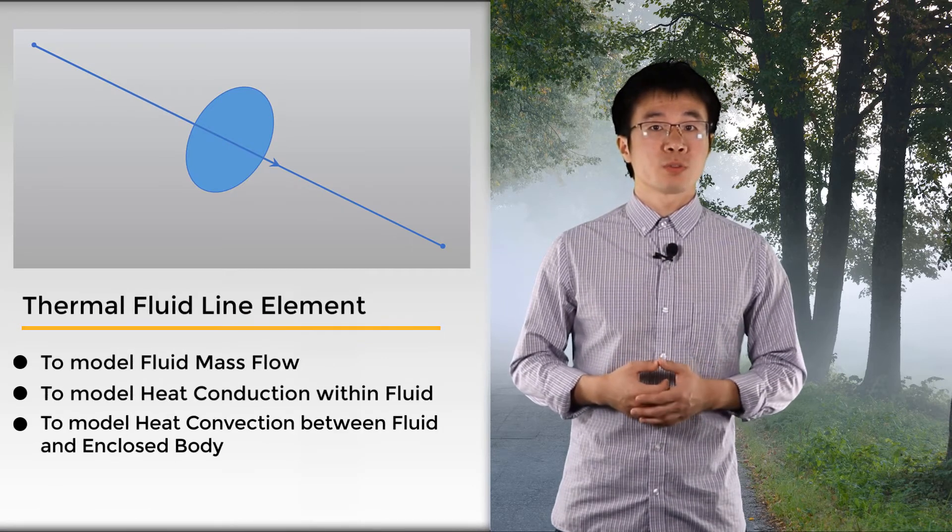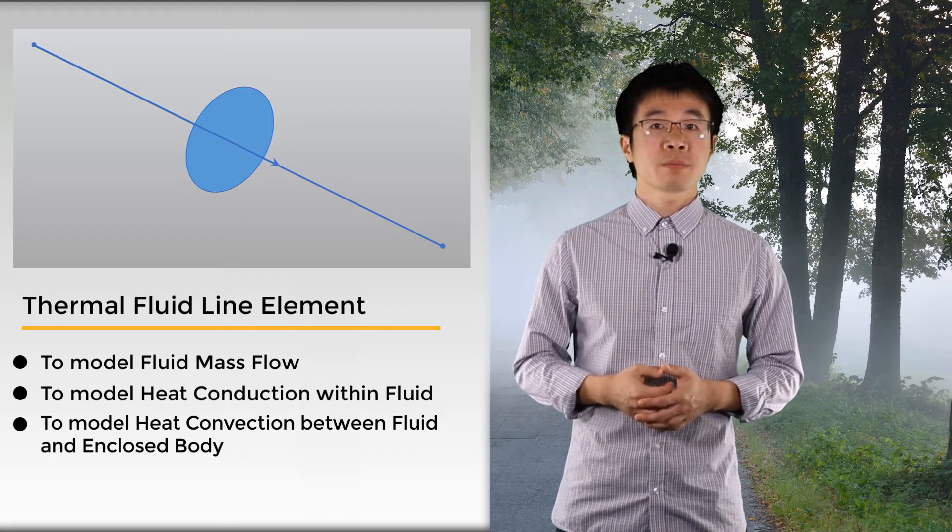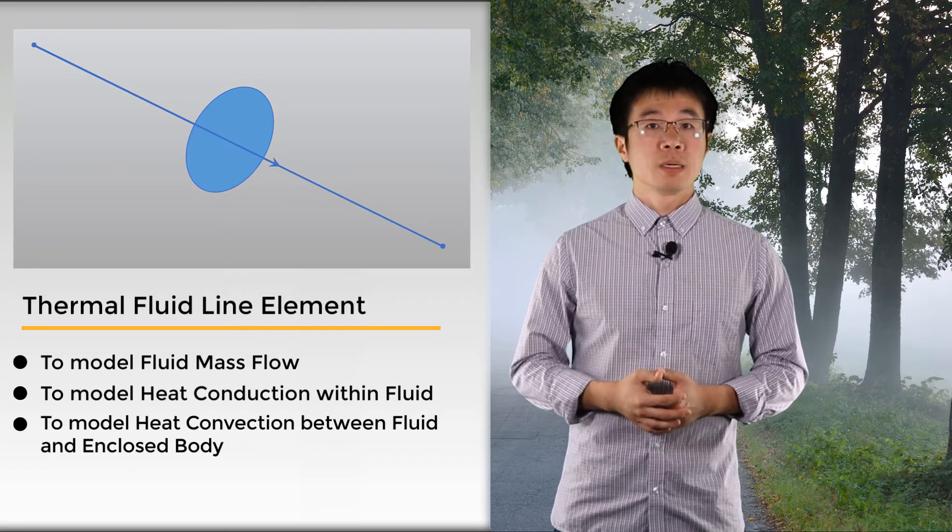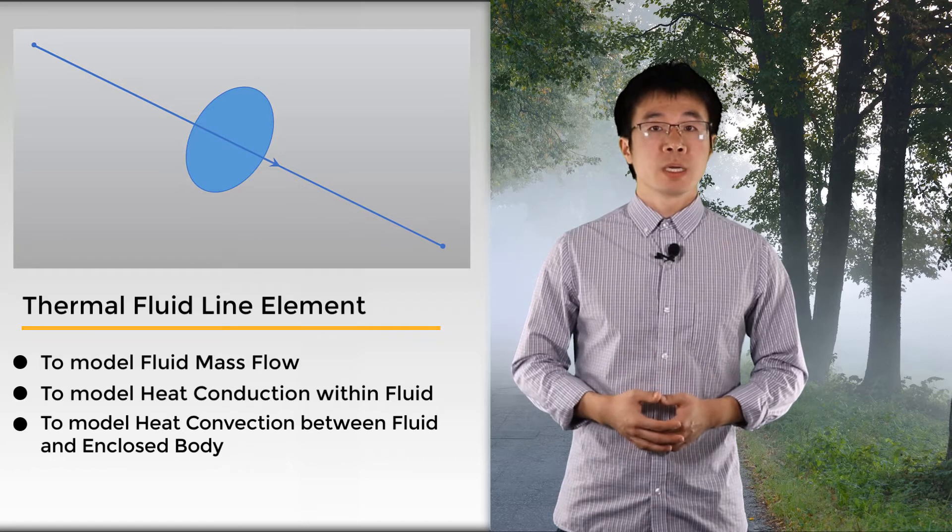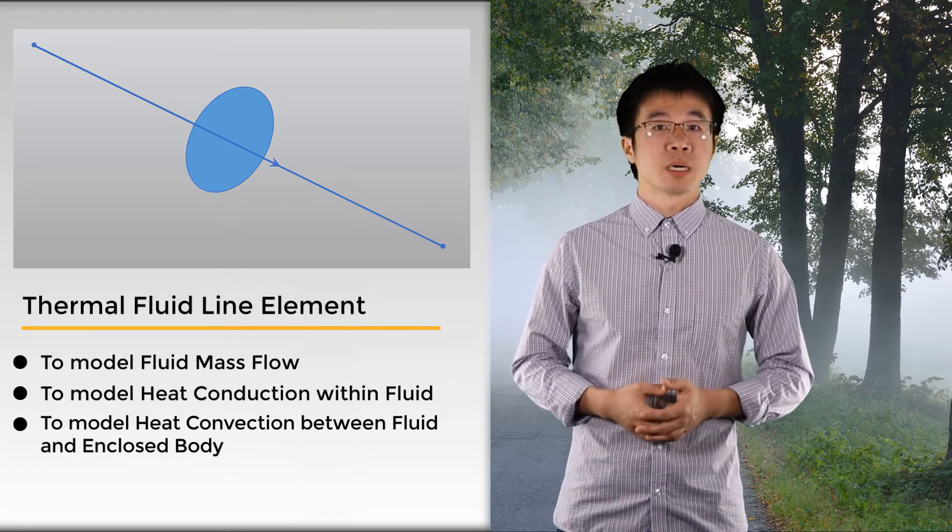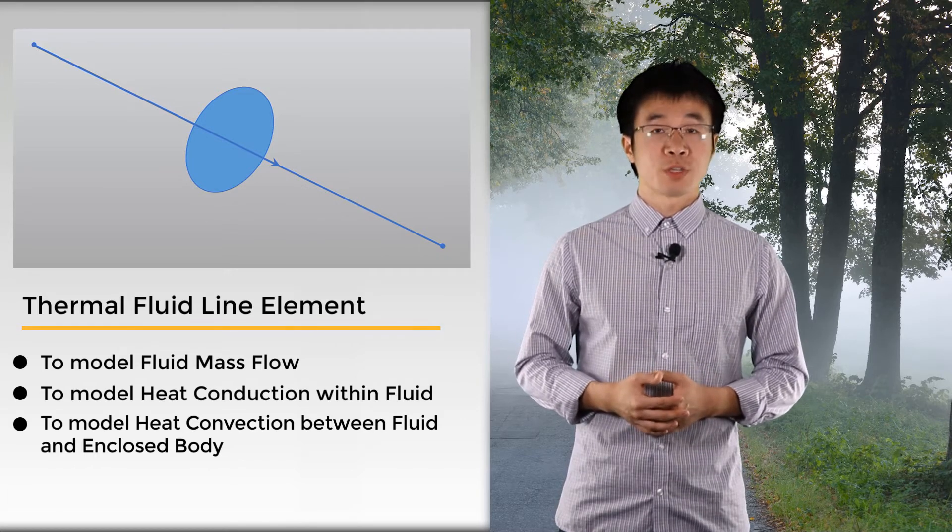However, CFD is computationally expensive. Alternatively, one can use 1D thermal fluid line elements to model the fluid mass flow in pipes and heat convection in the conduction-based solver, such as ANSYS Mechanical. These elements can provide sufficient accuracy of the mass flow, heat conduction within the fluid, and convection between the fluid and the enclosing body, while its biggest advantage is its cost efficiency.